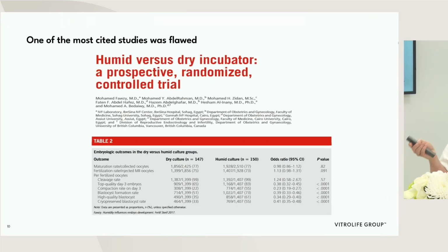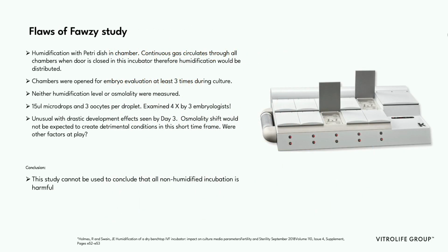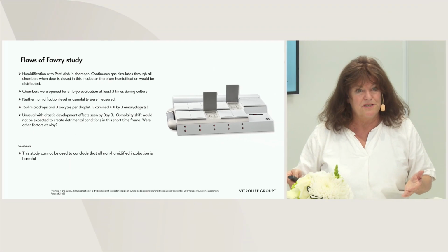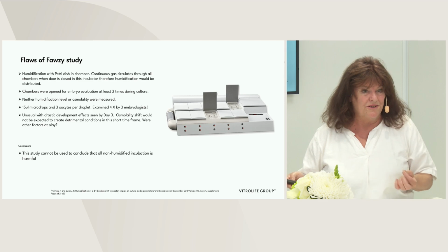This is the most cited study for looking at humidified versus non-humidified. This is the Fawzy study. However, there's very many flaws with this study. First of all, humidification was achieved apparently by putting a water dish in one of the chambers. And the problem with this is an incubator type where when you close the chamber, the air is recirculated all around. So given that humidity wasn't measured, it's very impossible to see if this was actually humidified because the air is circulating all around.